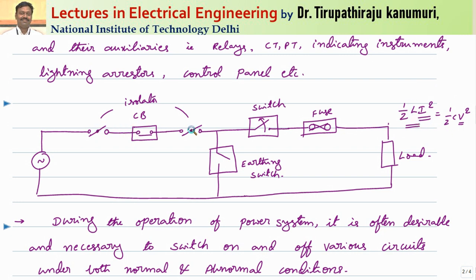Along with circuit breakers, there is one more device called the isolator. What is the difference between an isolator, a switch, and a circuit breaker? Let us take a circuit breaker — sometimes circuit breaker maintenance will be required. With respect to time, as you are operating it multiple times, the fixed and moving contacts may get damaged, or you may need to replace the liquid or gas inside the circuit breaker, test it, and repair it. Whenever you want to do the repairing, it should be completely disconnected from the supply. Even though you open your circuit breaker, one side will still be connected to the supply. If you want to completely isolate it from the supply, isolators are used. Generally, isolators are switches but having zero current carrying capacity, meaning you cannot open your isolator under load conditions or even under low load conditions, because they are simple conductors only, and if you try to open them under load conditions, they will damage the contacts of your isolators.